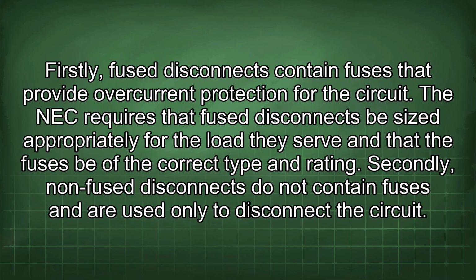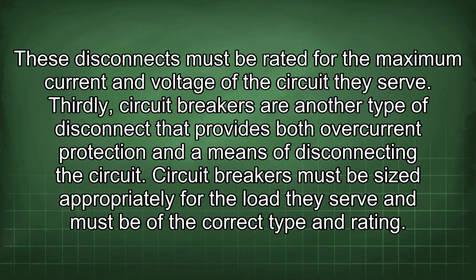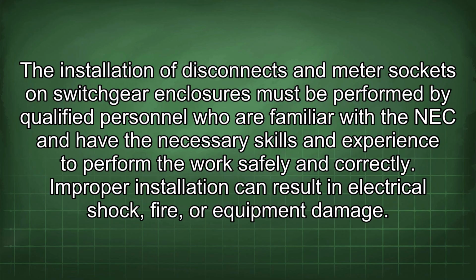Secondly, non-fused disconnects do not contain fuses and are used only to disconnect the circuit. These disconnects must be rated for the maximum current and voltage of the circuit they serve. Thirdly, circuit breakers are another type of disconnect that provides both overcurrent protection and a means of disconnecting the circuit. Circuit breakers must be sized appropriately for the load they serve and must be of the correct type and rating. The installation of disconnects and meter sockets on switchgear enclosures must be performed by qualified personnel who are familiar with the NEC and have the necessary skills and experience to perform the work safely and correctly.